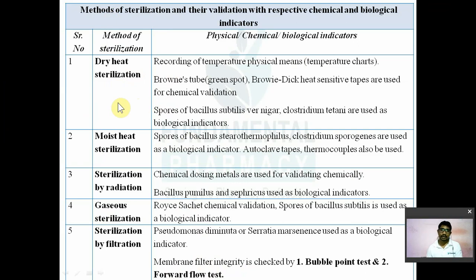Dry heat sterilization will be validated by three kinds of methods. First one is physical, so recording of temperature by physical means or temperature chart. It is a physical method for validation of dry heat. Then the second one is a chemical method for validation of sterilization by dry heat. That is Browne's tube. It is also a chemical method for validation of dry heat.